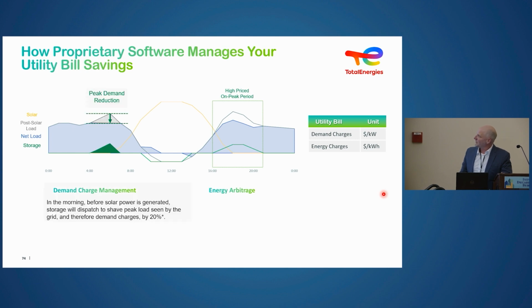One thing we can do is demand reduction. We can basically pinch that demand off from the customer by discharging the battery. You can see the green in the bottom is where we're discharging the battery, and that reduces the pull from the utility and the associated demand charges. That's one way we're able to improve the economics of the project with storage.